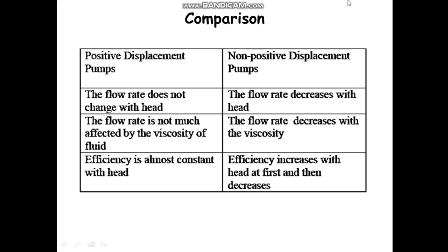Now if we compare positive and non-positive displacement pumps, the flow rate does not change with the head for positive displacement pumps. On the other hand, for non-positive displacement pumps, the flow rate decreases with the head. The flow rate is not much affected by the viscosity of the fluid in a positive displacement pump, whereas the flow rate decreases with viscosity for a non-positive displacement pump. For a positive displacement pump, efficiency is almost constant with head because there are no leakages, whereas for a non-positive displacement pump, efficiency increases with the head first and then decreases as the leakage keeps increasing.